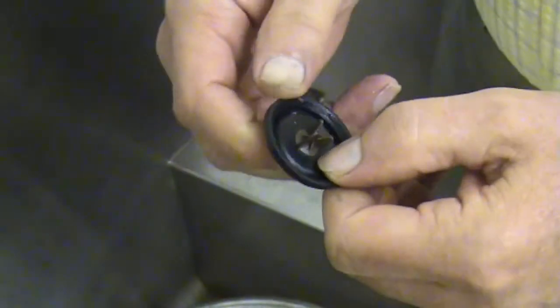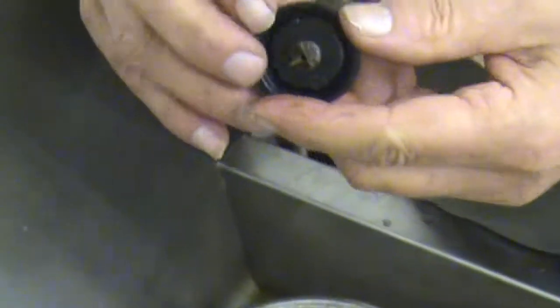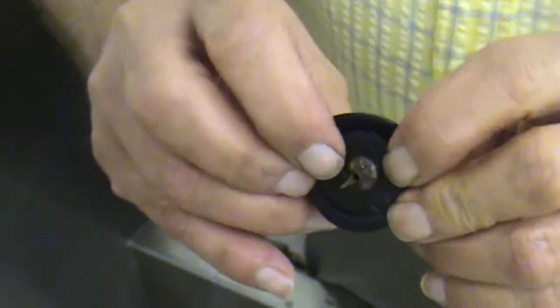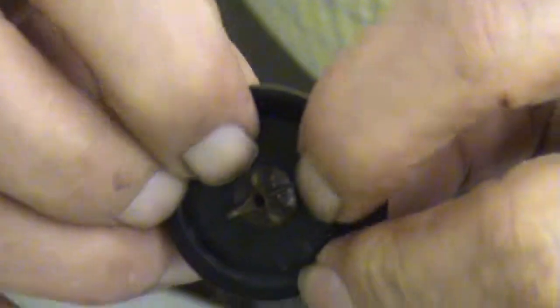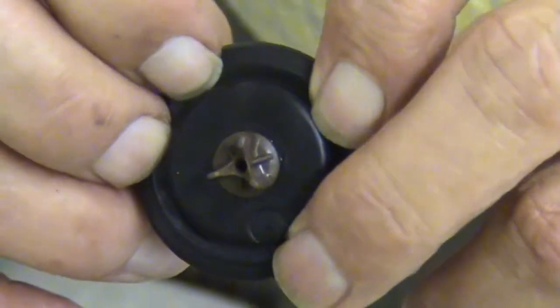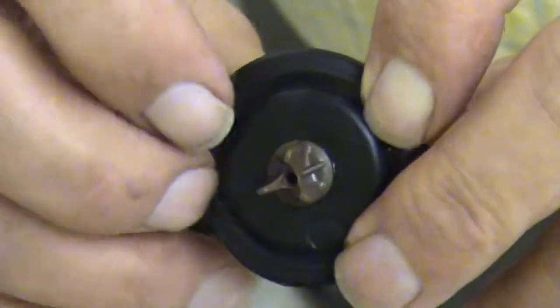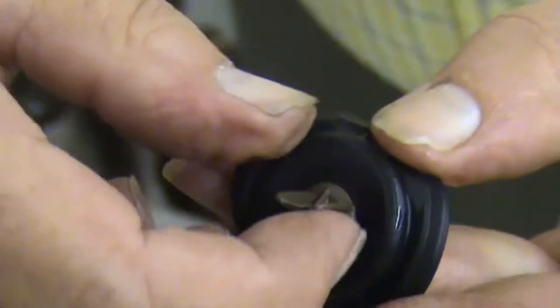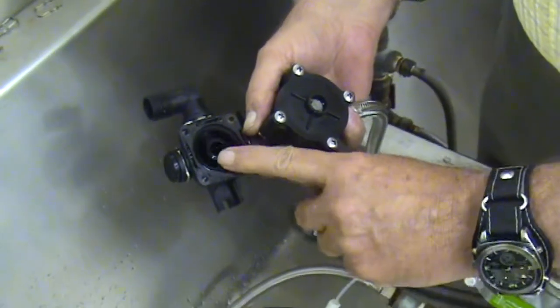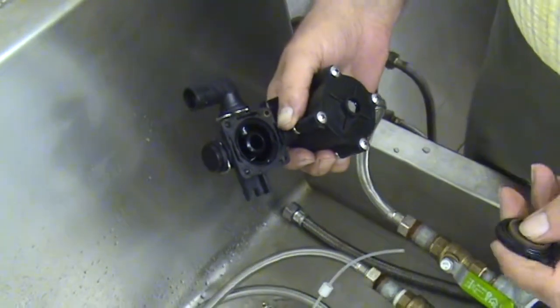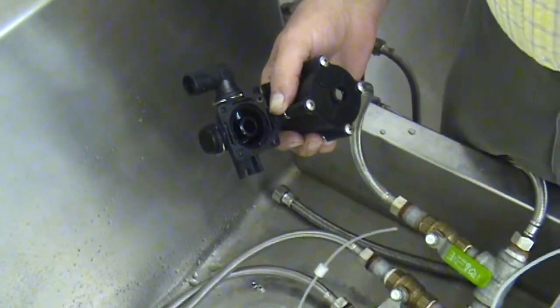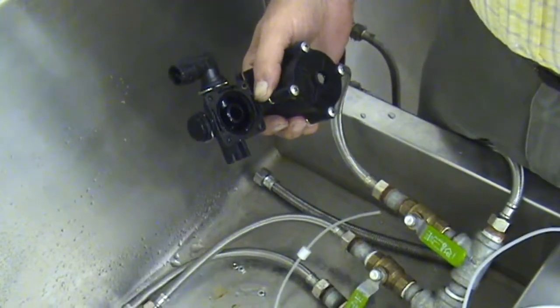Turn it around that slot so all the edges are even. And now if you look at this vane, you'll see that that rubber is backing underneath in that groove the way it should be. And the surface around the vanes is flat. That is your sealing surface that seats onto the seat of the valve here. If that rubber is off its post, it will not shut down no matter what you do.